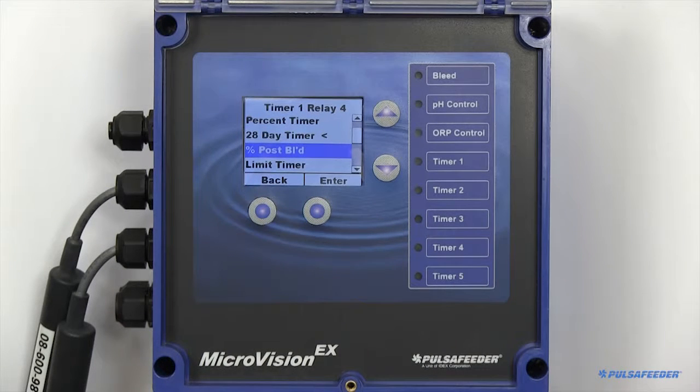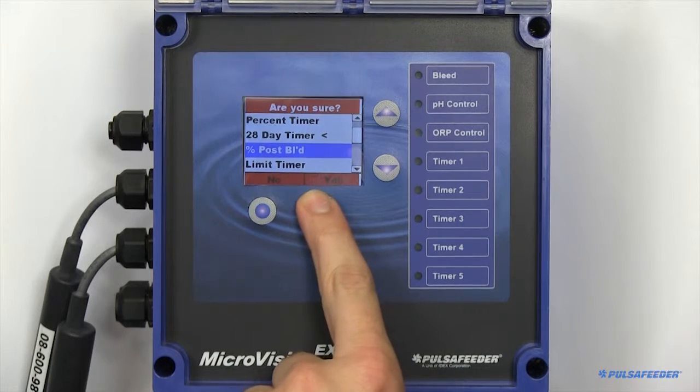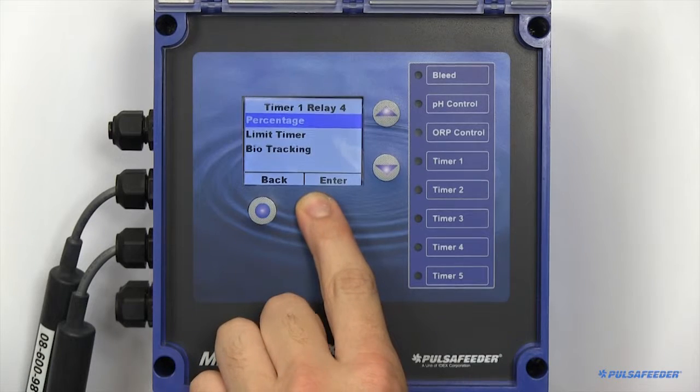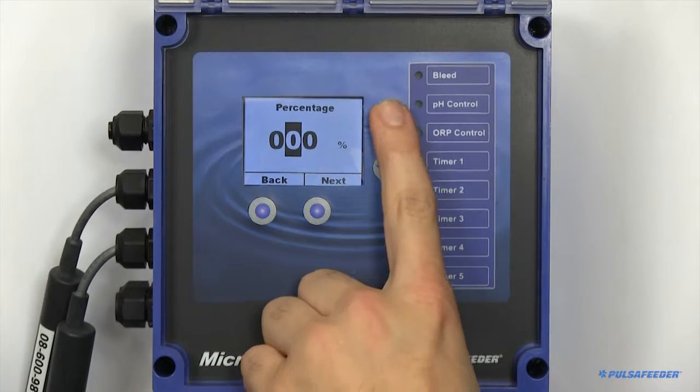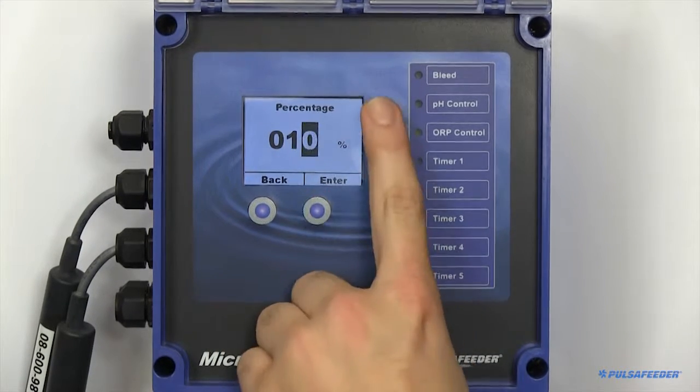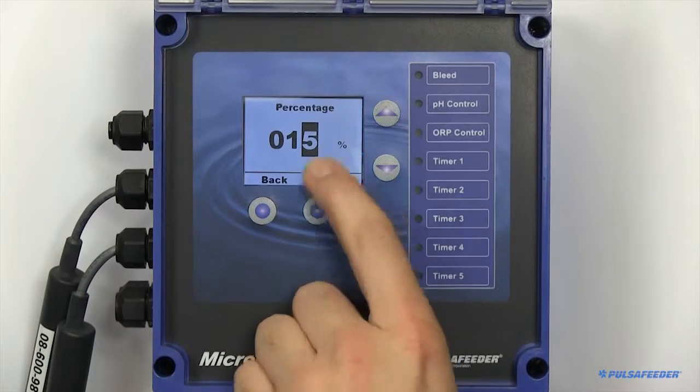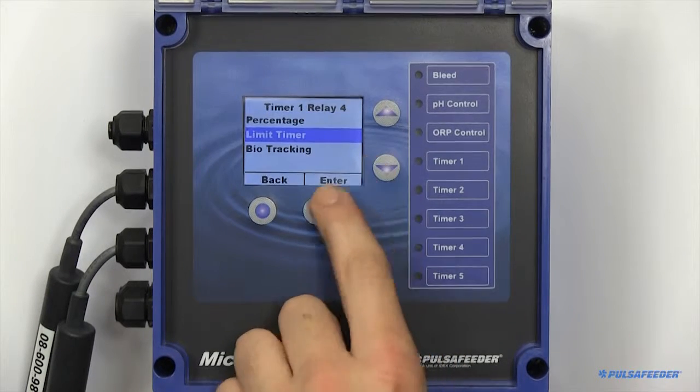Percent Post Bleed keeps track of the time the bleed relay is turned on. When that bleed shuts off, it will then bleed for the specified percentage. The timer also includes a limit timer to prevent overfeeding.